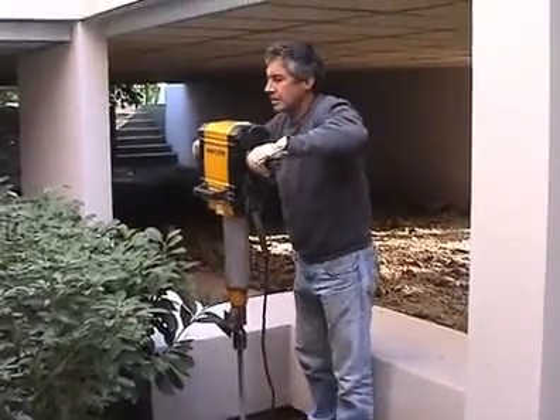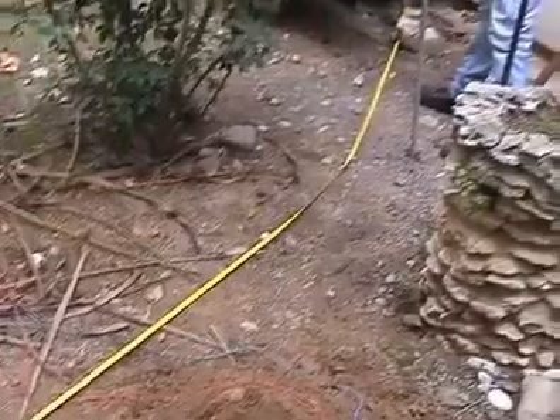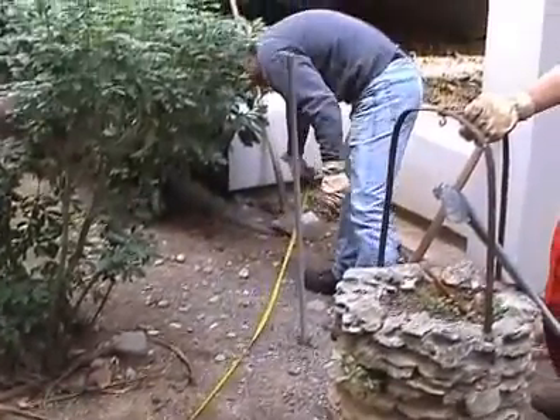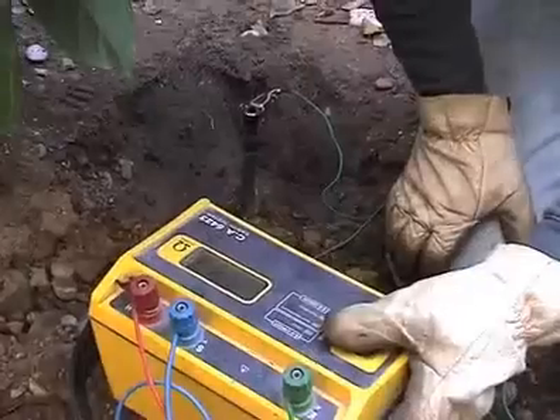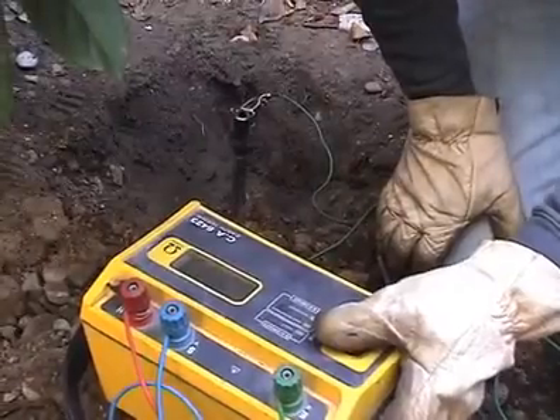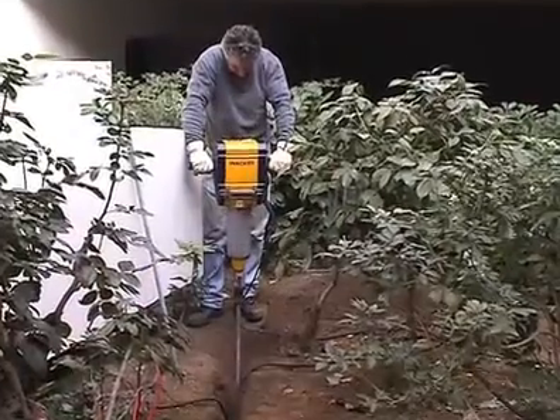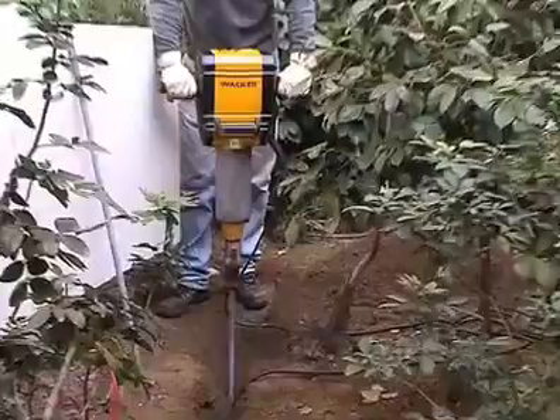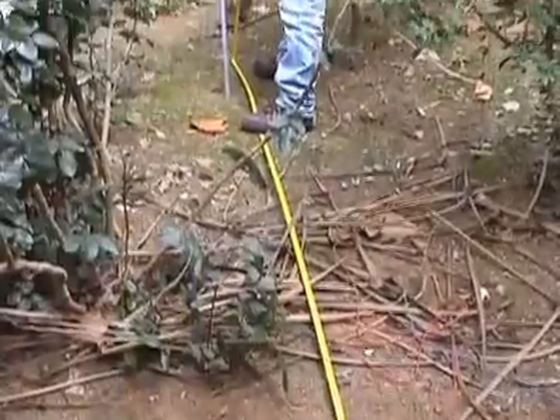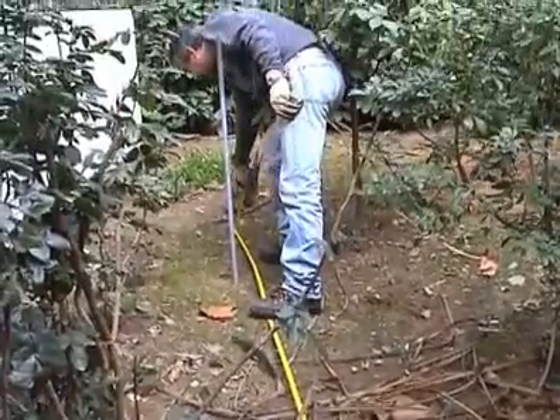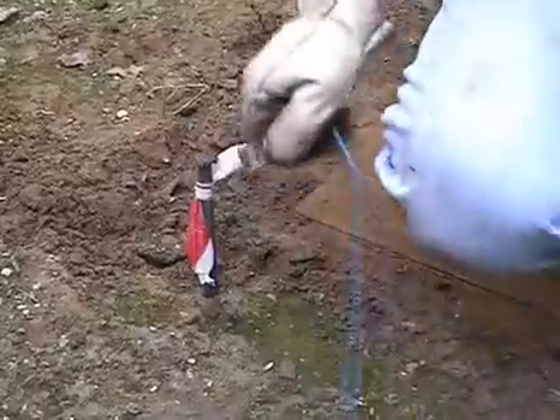An interim measurement of the earthing system allows us to continue with the installation of the second earth rod, which is located at least 3 meters away from the first one. Another measurement of the earthing system indicates that we need to continue with the installation of the third earth rod. The installation must be identical to the other rods and placed at least 3 meters away from the other 2.